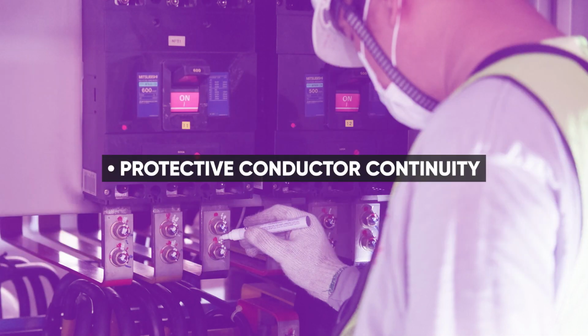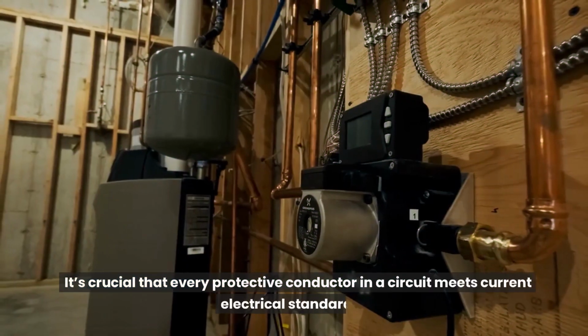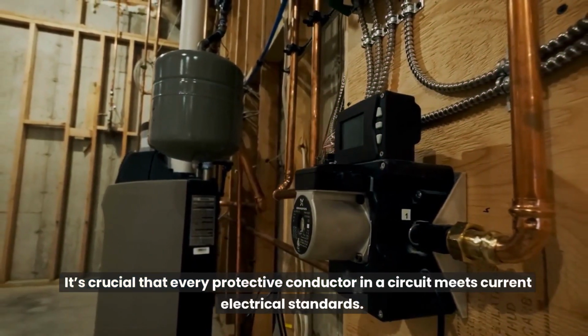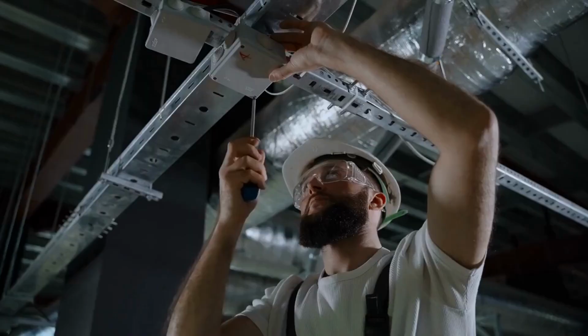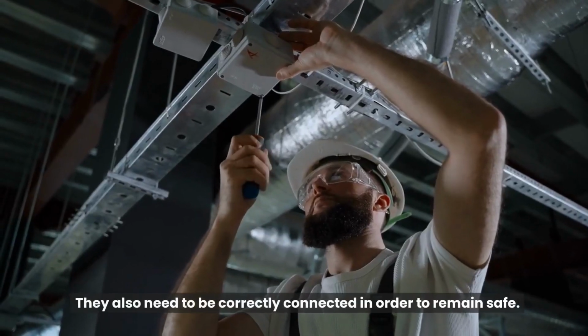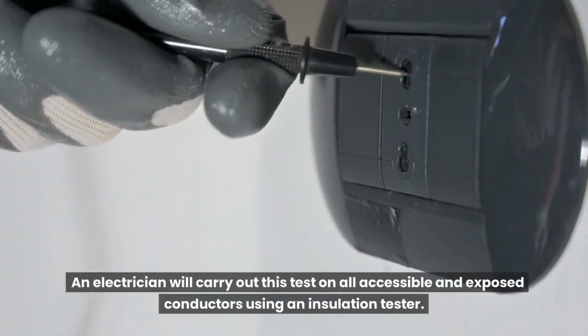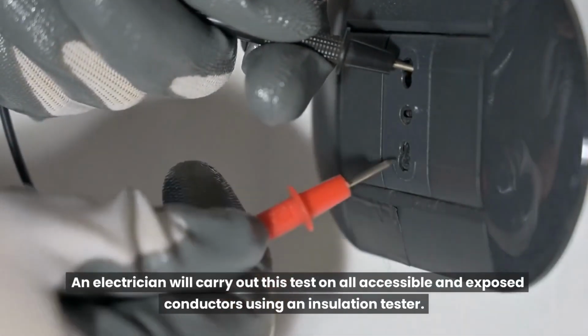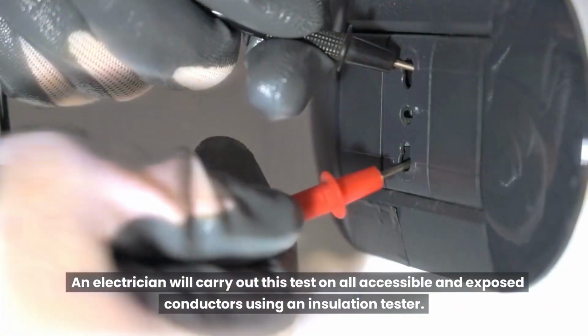Protective conductor continuity. It's crucial that every protective conductor in a circuit meets current electrical standards. They also need to be correctly connected in order to remain safe. An electrician will carry out this test on all accessible and exposed conductors using an insulation tester.